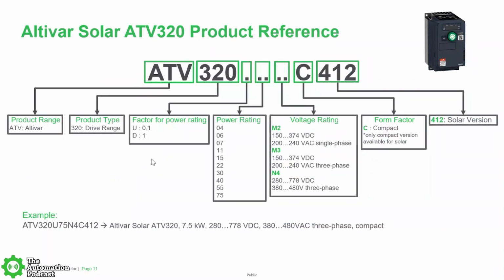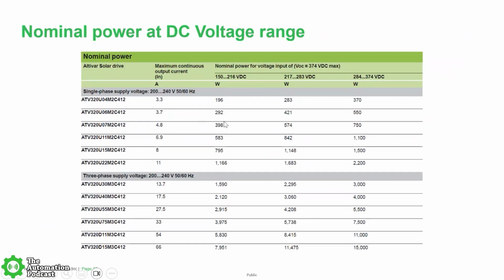For those familiar with Schneider nomenclature, the ATV320C is the same model number. The range changes here, and the 412 would be the identification, the difference between using a standard machine VFD versus a solar VFD. Now, this is important, especially when sizing the solar cells. There are a couple of ways we can do this. We've provided a solar sizer that can help with some general solar information, and the cut sheet, to make sure we have the right number of rows and arrays to power the pump or the machine. So this is the min and the max range for the solar cells.